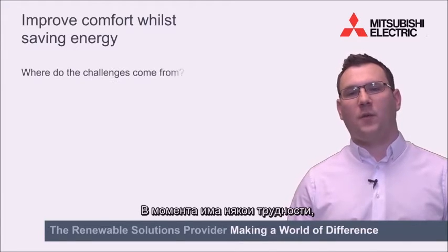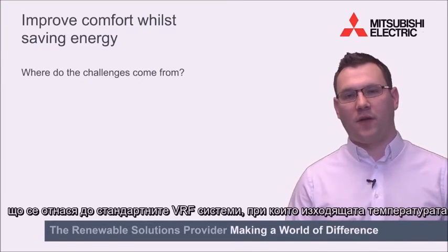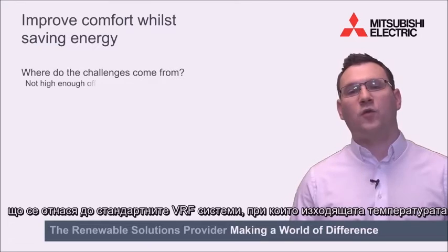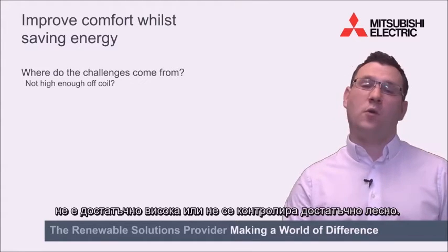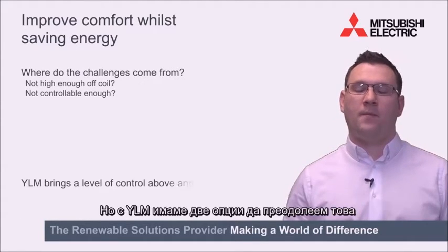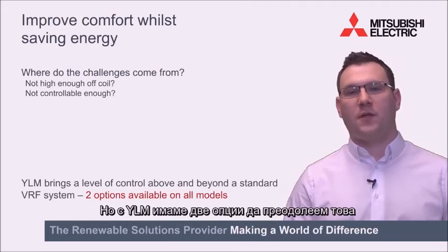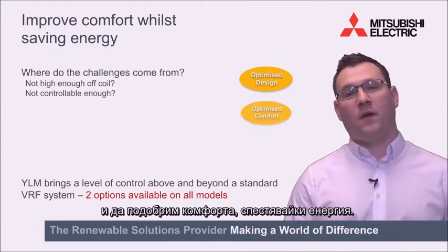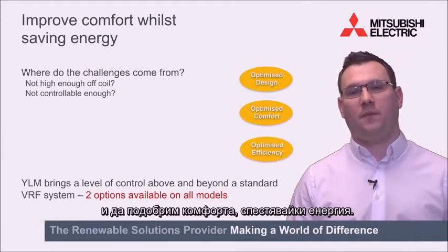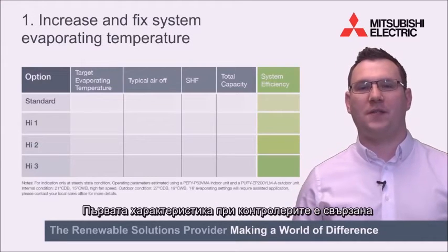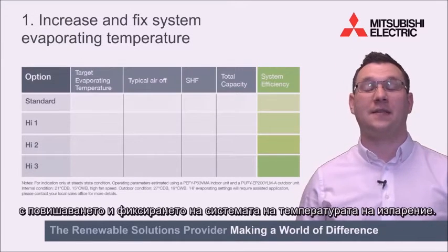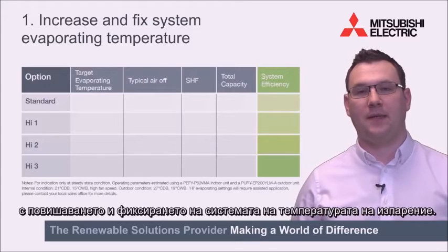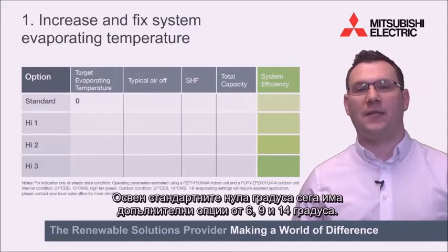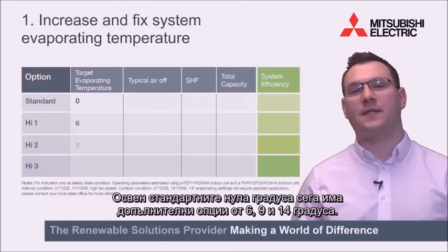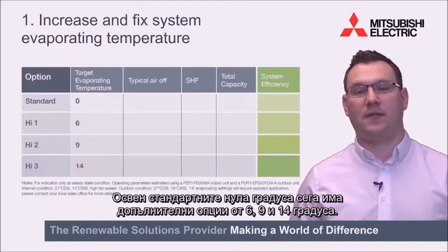Currently on the cooling side we have challenges sometimes in traditional VRF systems whereby the off-coil temperature is not quite high enough or it's not quite controllable enough. But with YLM we have two options to overcome this and improve the comfort whilst also saving energy. The first of the control features is around increasing and fixing the system evaporating temperature. The standard 0 degrees now has additional options of 6, 9 and 14 degrees.